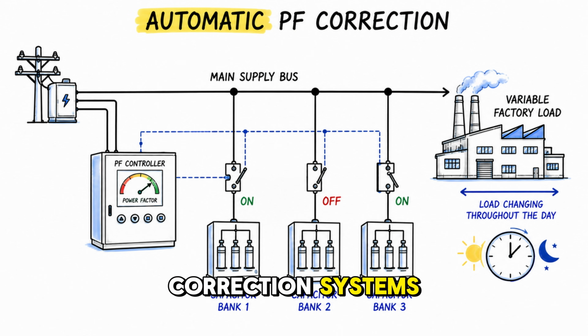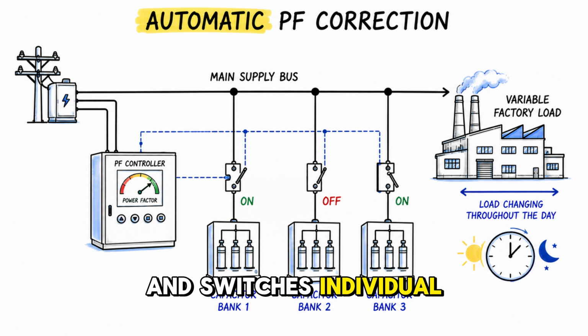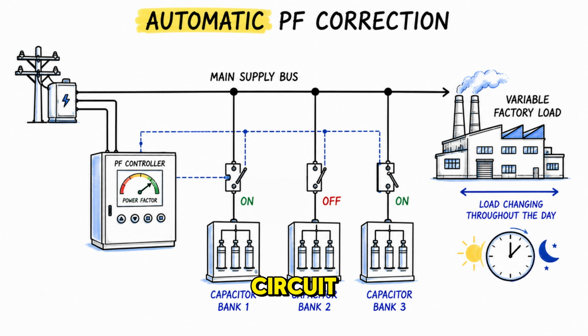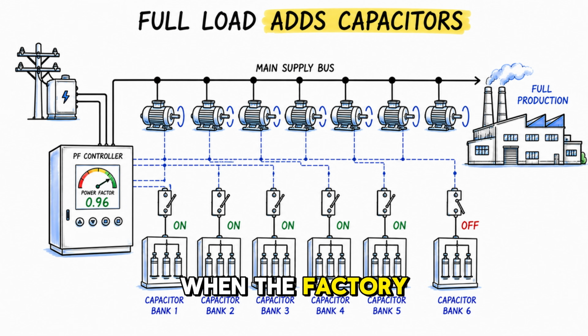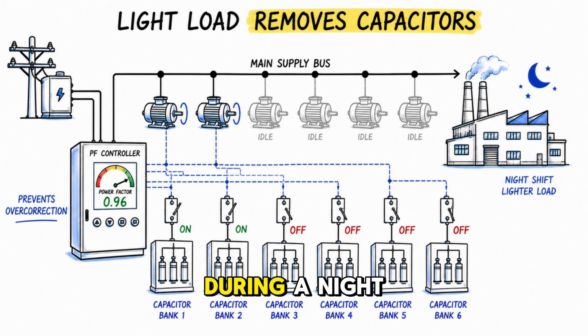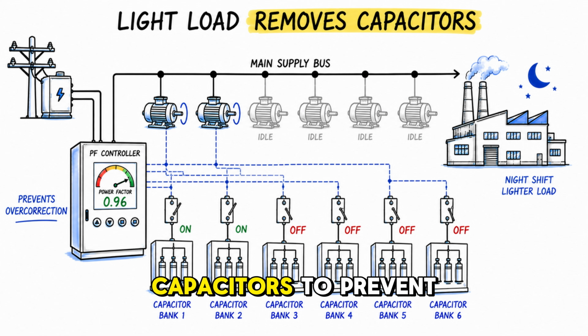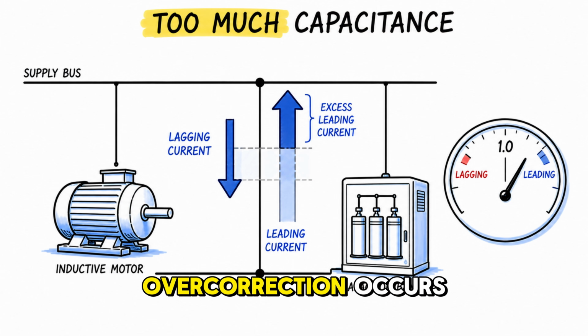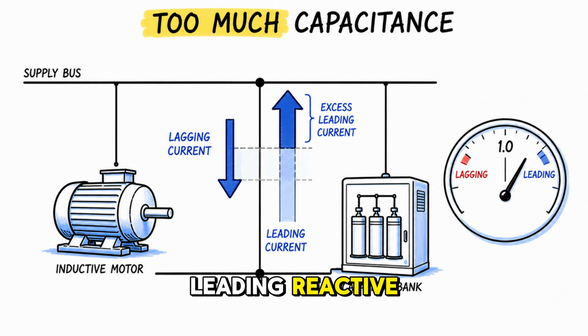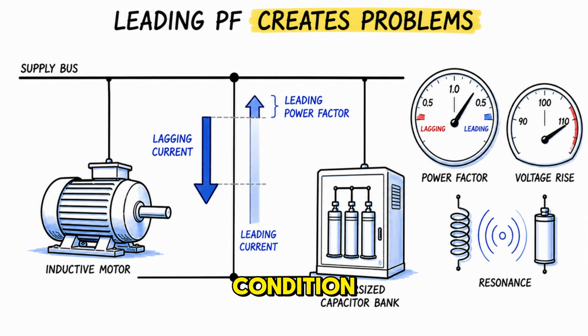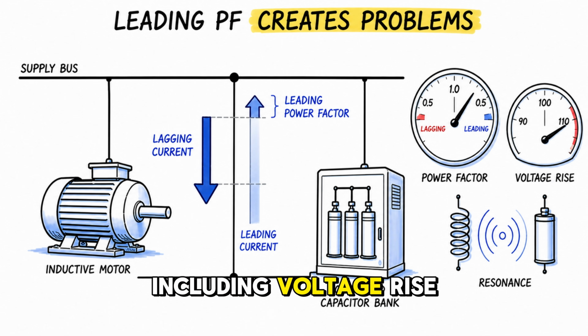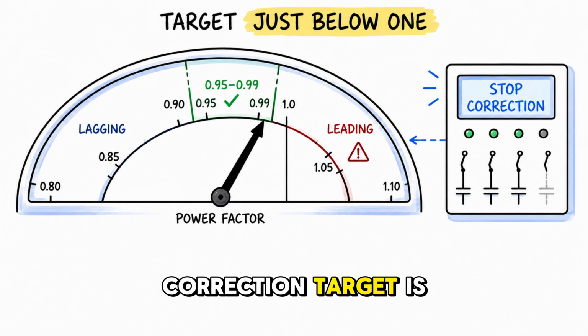Automatic power factor correction systems go further. They use a controller that monitors power factor in real time and switches individual capacitor banks in and out of the circuit as the load changes throughout the day. When the factory is running at full production with all motors operating, the controller adds more capacitors. During a night shift with fewer machines running, it removes capacitors to prevent overcorrection. Overcorrection occurs when capacitors provide more leading reactive current than the motors need. In such a condition, the power factor becomes leading rather than lagging, and creates a different set of problems, including voltage rise and resonance. For this reason, the correction target is always slightly below 1 rather than exactly 1.